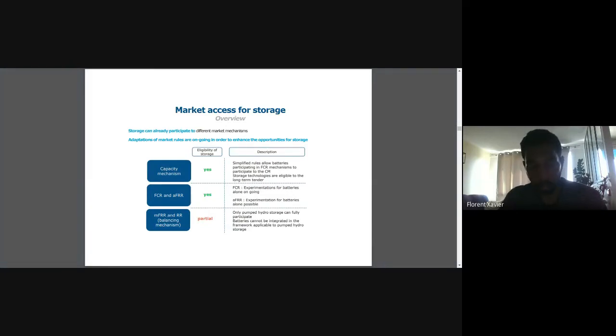The last market offer is the mFRR, or RR, more of a balancing mechanism - it's called the tertiary frequency control. It's a long-term control, so that's why I mentioned it's only partially eligible. For batteries, it's more complicated to participate in this kind of mechanism because the time scale is too large, and if they want to participate they need to oversize the batteries, which can have a big impact on cost. So only pumped hydro storage can fully participate in this market.